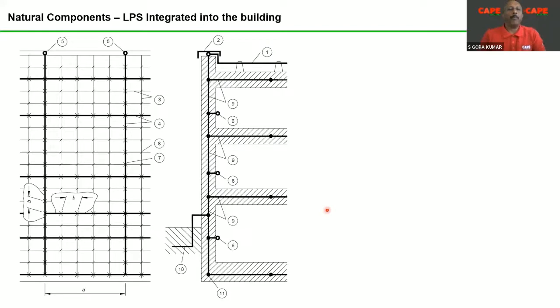Now, how do you make a building with natural components? What you are seeing in the picture is an RCC building, maybe a multi-floor building. At the top of the building, you have the air termination, which is always exposed because lightning must hit the air termination, and probably some covering for the parapet. I have taken the picture from the standard. In India we don't have the habit of covering the parapet with this kind of conductor, but we have the habit of a metallic handrail on the parapet. If you have a metallic handrail on the parapet, it will do the job of air termination.